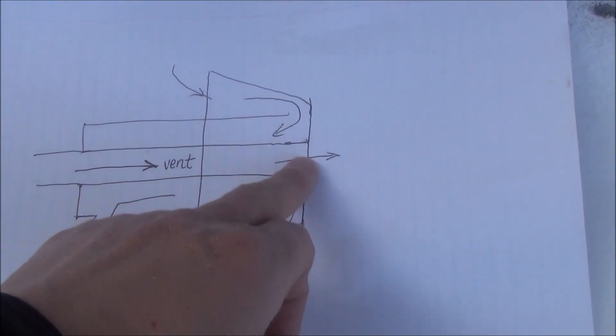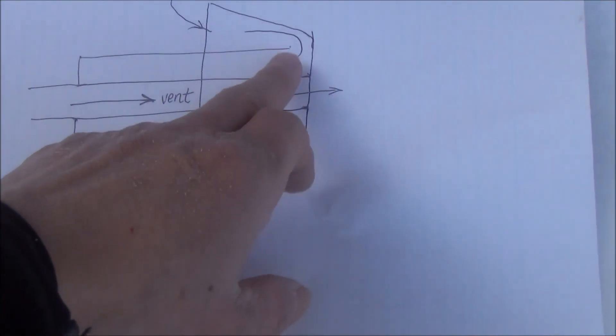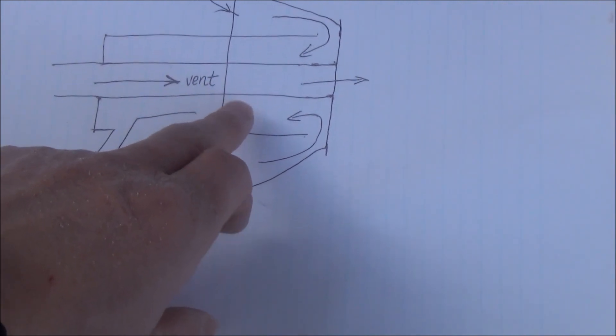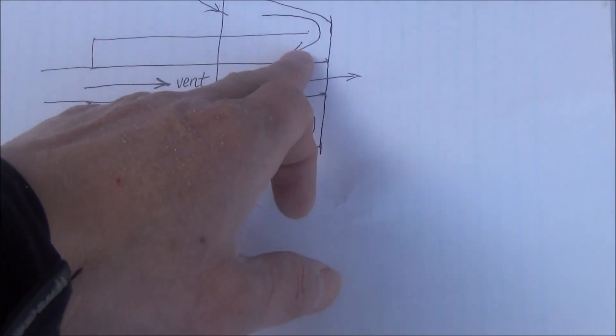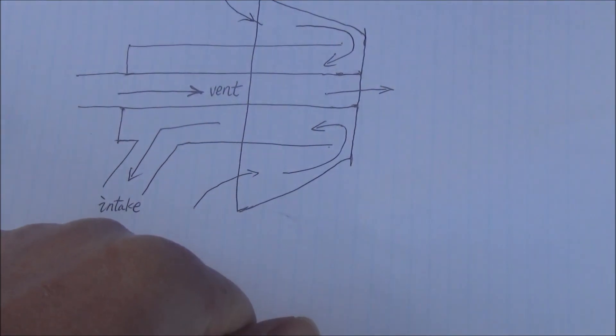So the intake was blocked and the heater cannot kick in. With this one blocked, the pressure has some problem — the pressure switch cannot detect good pressure. Then the signal says the pressure switch has a problem. Now with this cleaned, pressure gets to normal, the pressure switch works, and then the heater works. So it sounds like my pressure switch maybe had no problem at all. I wasted my time and my money and my technician's time.